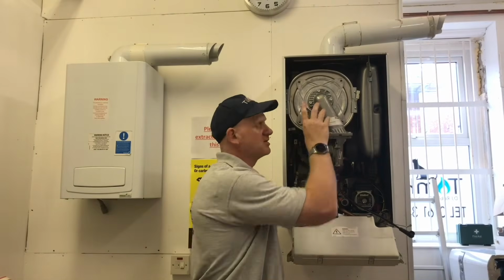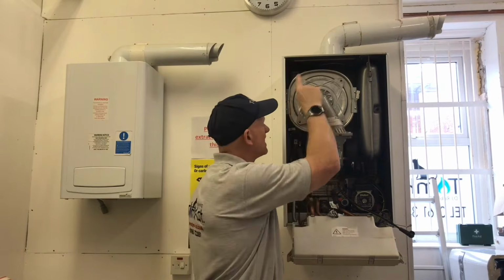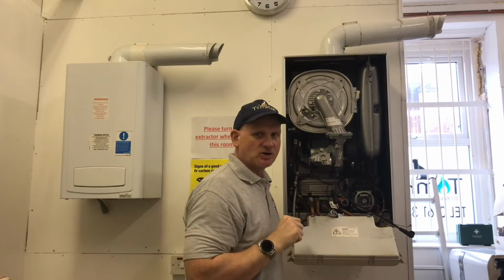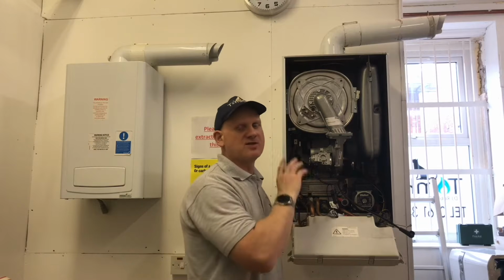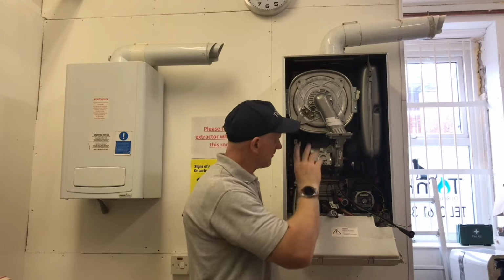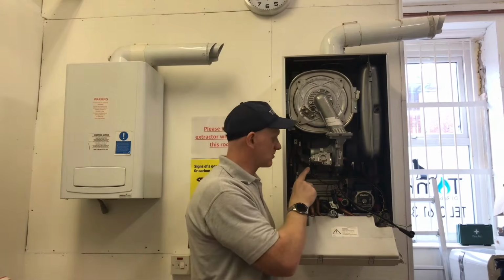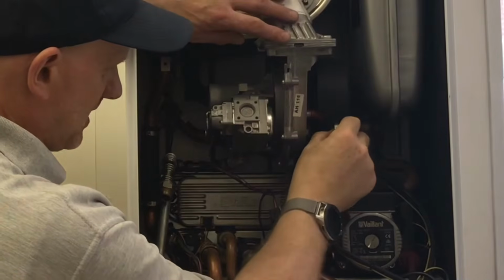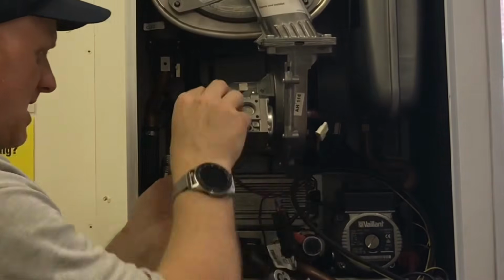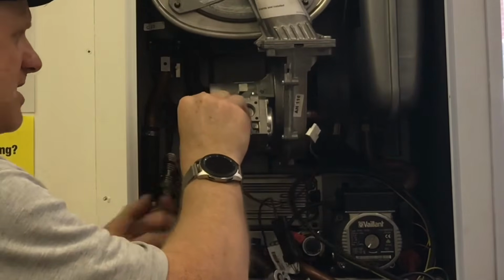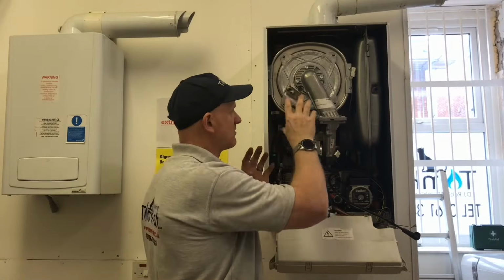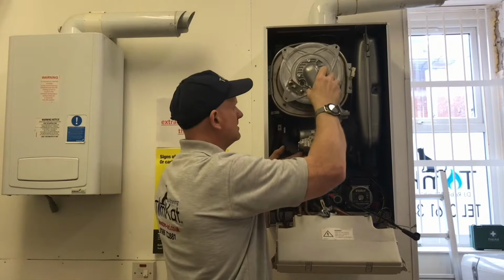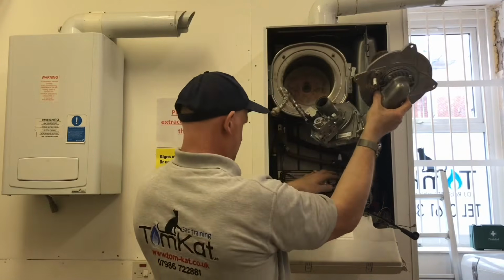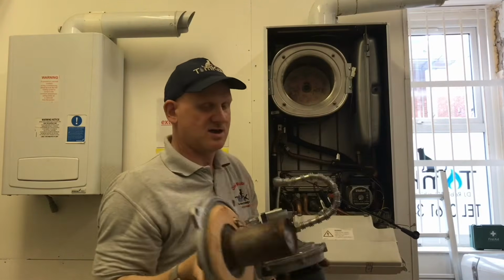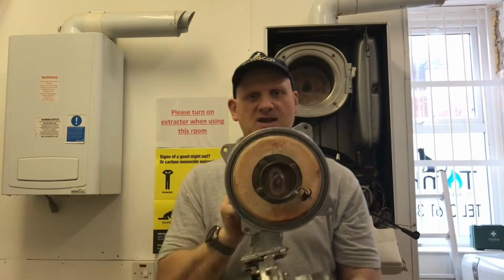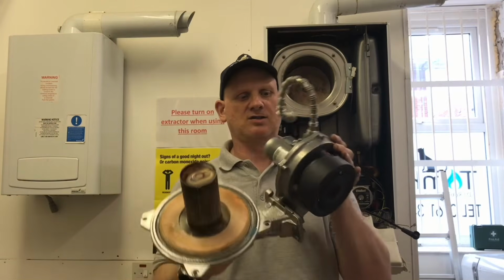Now before we actually remove this out of here, we've taken the nylock nuts off. These nylock nuts will need to be replaced every time you take this burner door off. So before we remove that, we need to remove some electrical connections. We've basically got one on the fan here, and we've got one on the gas valve here, and that's it. Okay, now this should pull straight off. Which it does, okay? So you can now see the burner in all its glory.